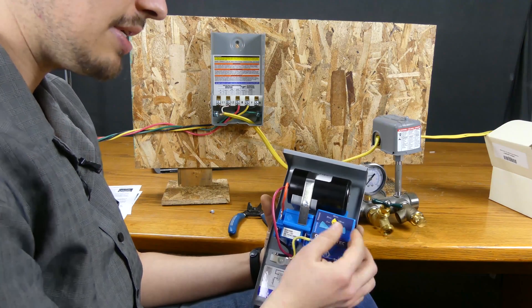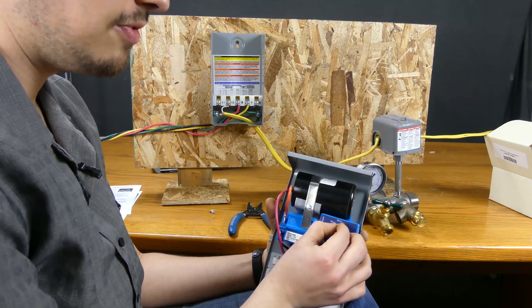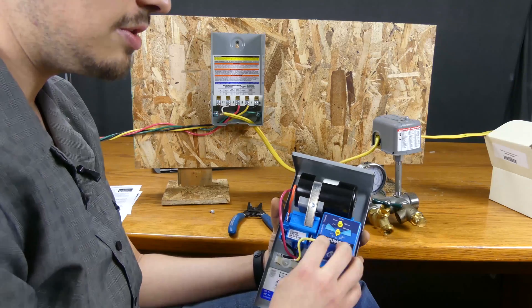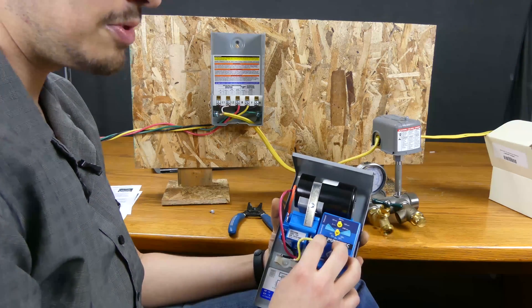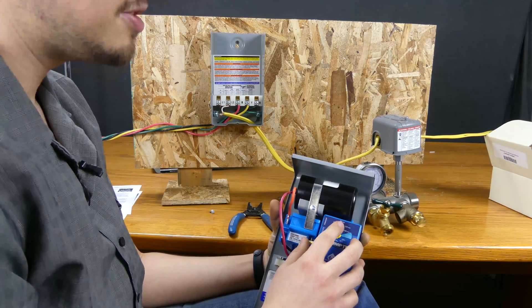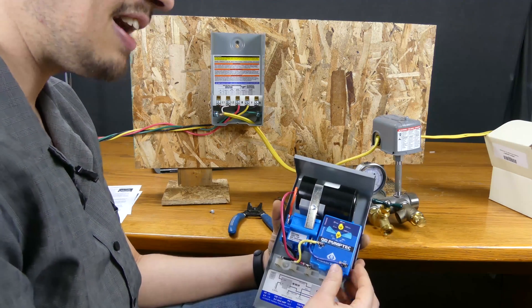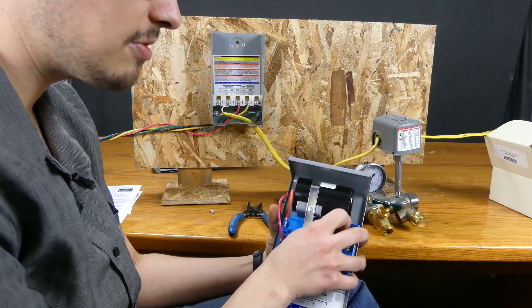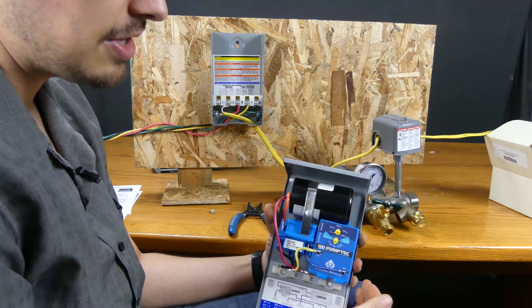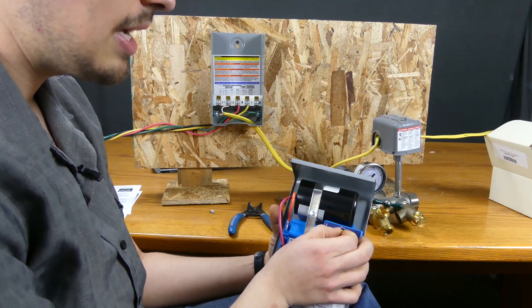And then the only other adjustment here is the timeout, so it's default to 60 minutes. So when this trips the pump you're going to have a 60-minute timer that starts and then the system will turn back on after that 60 minutes. This can be increased as far as 240 or decreased as low as two minutes.